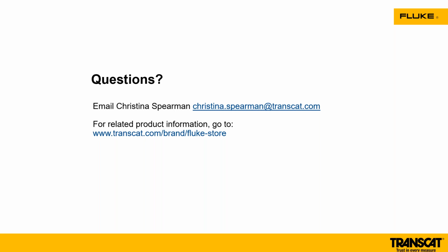Good question. All right, looks like we have another one. If you are wearing EH rated boots, does that impact the function of a non-contact voltage detector? Yes, it does, because you've got enough insulation and resistance in your boots that you're not going to be a good ground reference. Same with gloves. All of that plays into that value. So especially with the T6 and the 377, like I said, we specifically give you a common ground wire to ground out.